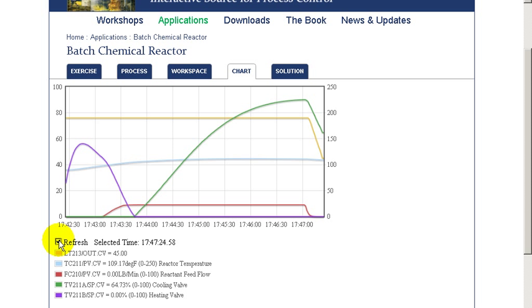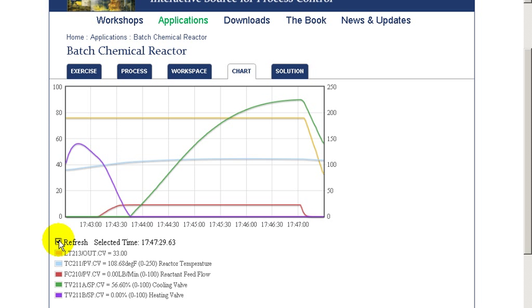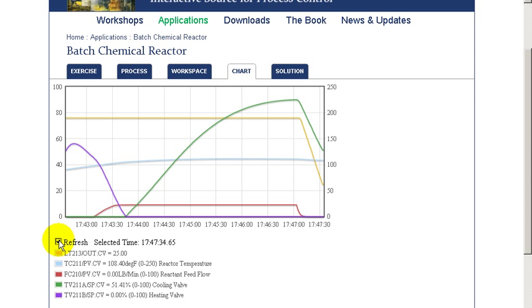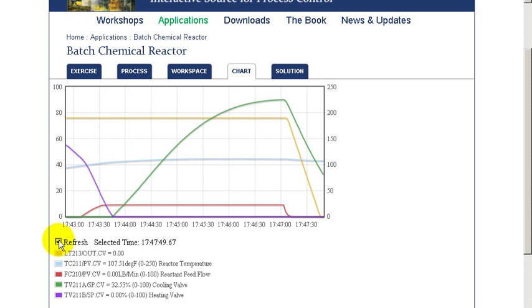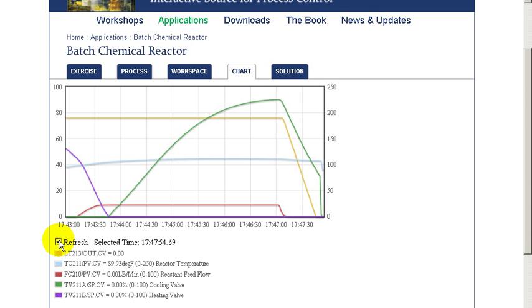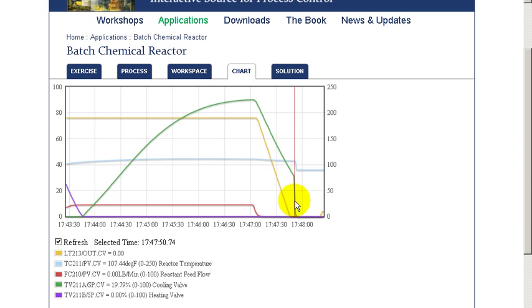As the level starts to fall, you notice that the temperature controller is automatically just closing the temperature valve, since there's less material to cool here. And at the point where the vessel is completely empty, then the batch logic automatically closes the cooling valve by adjusting the temperature controller output.